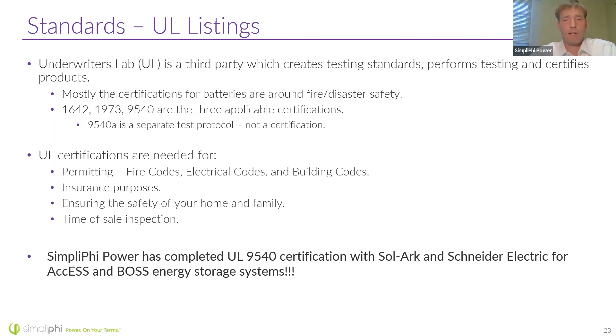They're needed for insurance purposes as well. If you're going to have fire insurance on your building and you've installed batteries that don't have the UL 9540 certification, the insurance would not cover you. So you want to make sure you meet all of these conditions, and of course the building inspector is going to be inspecting for this as well.